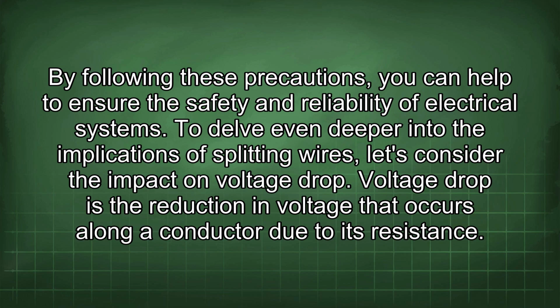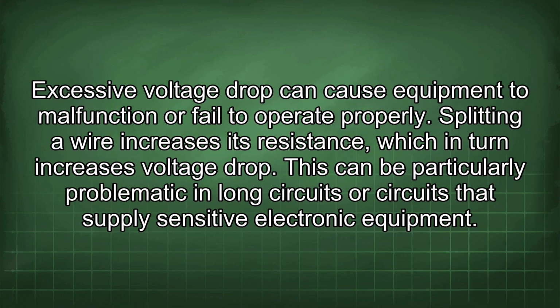To delve even deeper into the implications of splitting wires, let's consider the impact on voltage drop. Voltage drop is the reduction in voltage that occurs along a conductor due to its resistance. Excessive voltage drop can cause equipment to malfunction or fail to operate properly. Splitting a wire increases its resistance, which in turn increases voltage drop. This can be particularly problematic in long circuits or circuits that supply sensitive electronic equipment.